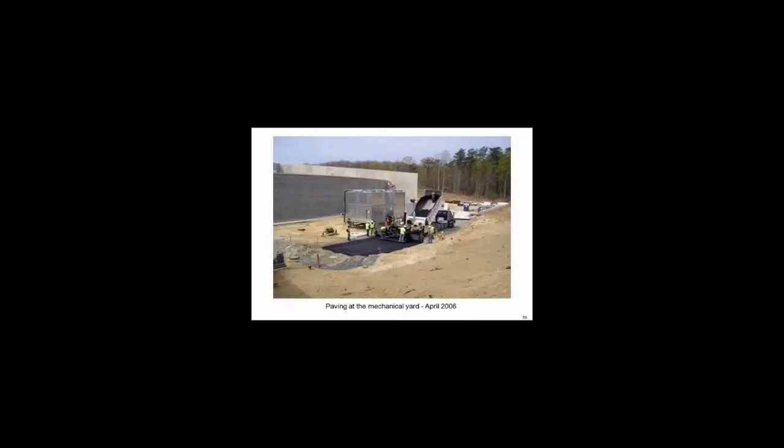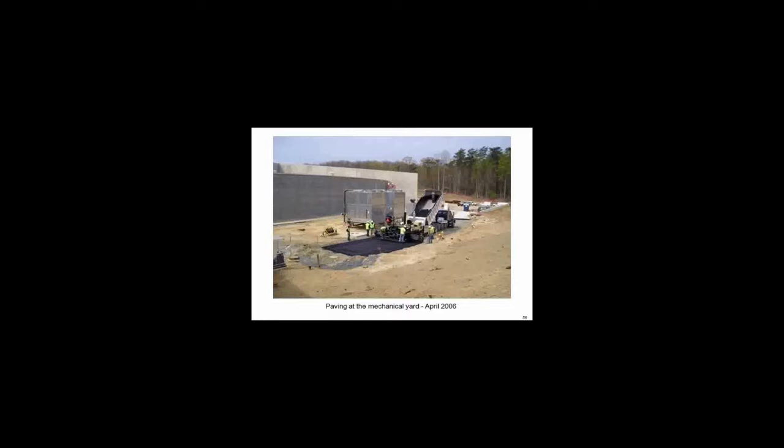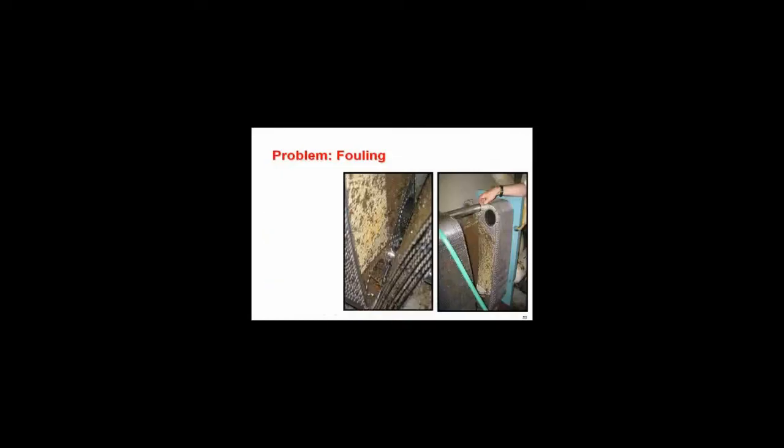If you're going to put in a heat exchanger like this, it's not going to last long, you're not doing your job. Don't get mad at me, but you're really not paying attention to the real world. Here's the real world for you. Here's a typical picture of a job site. A couple of cooling towers, basically the paving's been done, the general contractor wants to turn the building on and dry it out. How many times have we heard that comment? So where do you think all that red clay is going to go if there's any kind of wind going on if we turn on the tower? To make a long story short, you'll see what happens. So the message is anything in the air in a cooling tower is going to wind up in the sump of the tower. This is to the extreme, I know, but I'm trying to drive a point home to you. You see what happened to the plates on the job site, they immediately got fouled.